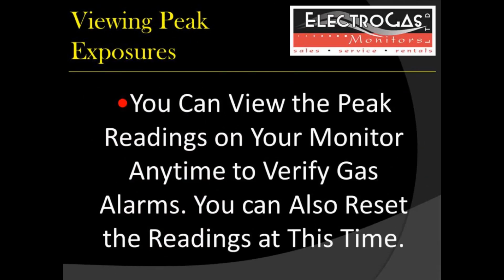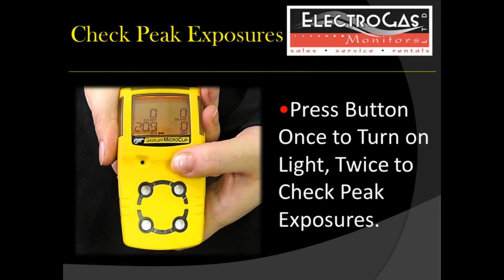You can view the peak readings of your monitor at any time to verify gas alarms. You may also reset the readings at this time. To begin checking peak exposures, press the blue button twice. The first will turn on the backlight, and the second will start the function.